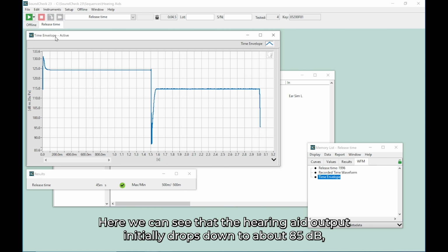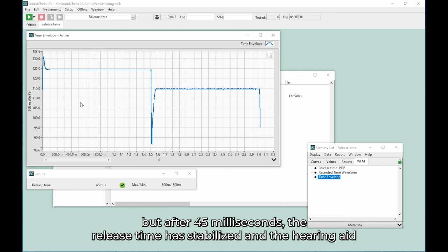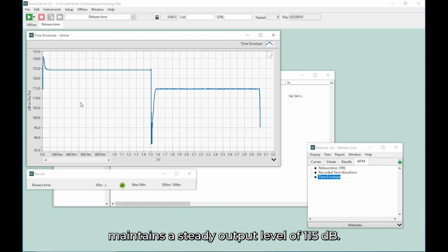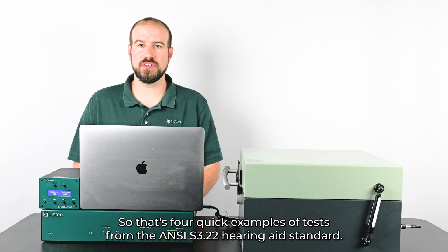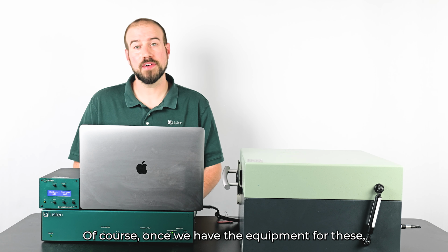Here, we can see that the hearing aid output initially drops down to about 85 dB, but after 45 milliseconds, the release time is stabilized and the hearing aid maintains a steady output level of 115 dB. So that's 4 quick examples of tests from the ANSI S3.22 hearing aid standard. Of course, once we have the equipment for these, there are many other hearing aid tests that you can run using the same test setup, and you can configure tests for the complete ANSI S3.22 standard in SoundCheck.